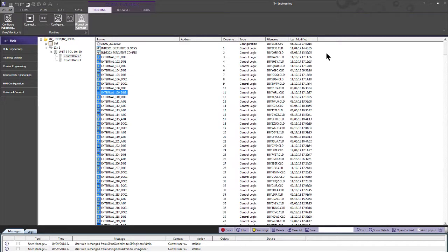For this, you'll need a copy of the calibration sheet, which can be found on the share drive under South, Operations and Maintenance, Records, Logs, Calibrations. I'm going to be referencing the calibration sheet for instruments on units. And just for today's example, we're going to use a PT004 on the Alpha engine. Your power turbine thrust balance pressure, which is a 0 to 100 PSI transmitter.